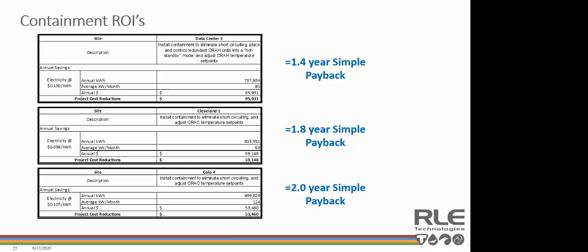True return on investment or even simple payback on a containment project can be pretty hard to calculate accurately. Things like peak versus off-peak electric consumption, seasonal rates, and rate discounts offered to customers for reducing demand really all factor into the overall electric rate paid. And even when you can find that information, you still need to understand the actual baseline energy consumption of cooling units prior to project implementation so you can really determine the actual savings of making some proposed changes to the cooling unit set points, and possibly, if you've got enough redundant cooling, setting some units in standby mode. This really requires energy monitoring of the cooling units or chiller plant over time before any changes can be made.